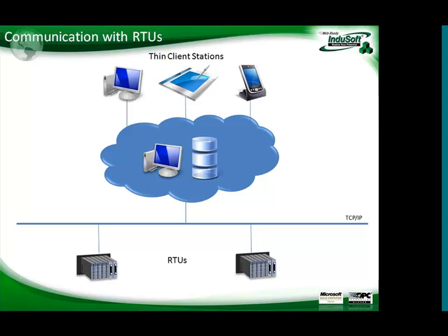Then this server running InduSoft Web Studio and collecting data from the remote RTUs saves data to the database, and using the web solution from InduSoft, this information can be made available to remote thin clients. InduSoft Web Studio supports 3 different types of thin clients. One is what we call the web thin client. You open Internet Explorer on a remote computer, type the URL for your server, which could be the virtual server running on the cloud, and then you have access to the graphical screens, online information, and history information, just as if the server was running on a physical machine.